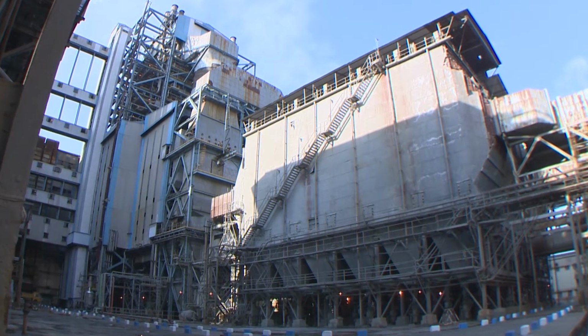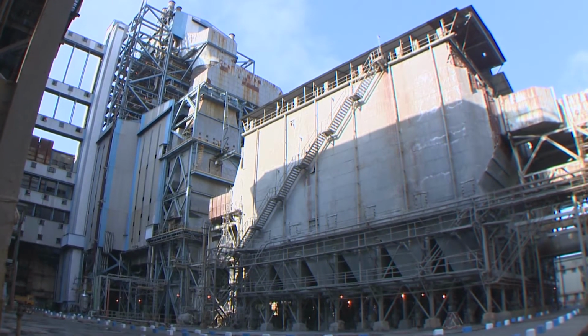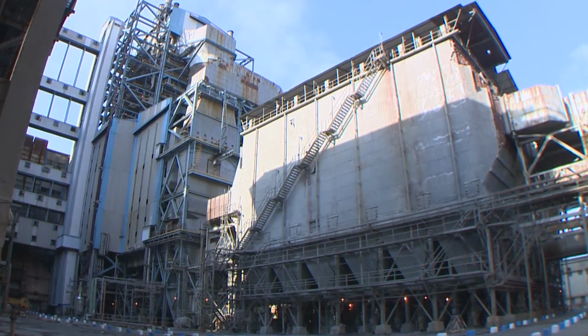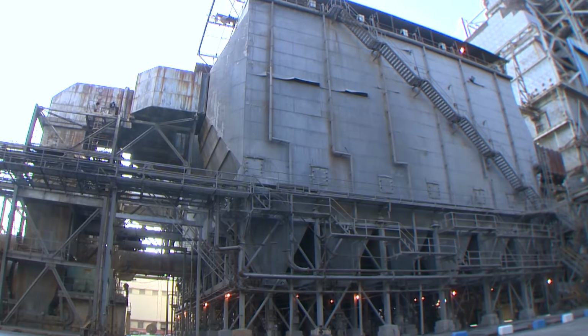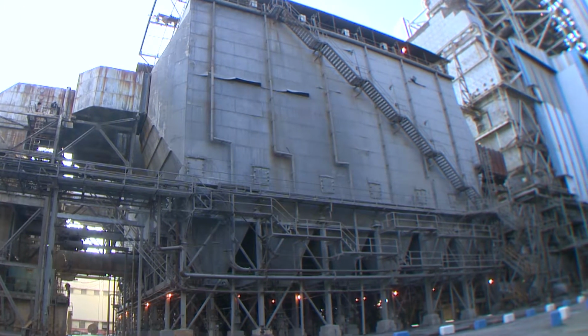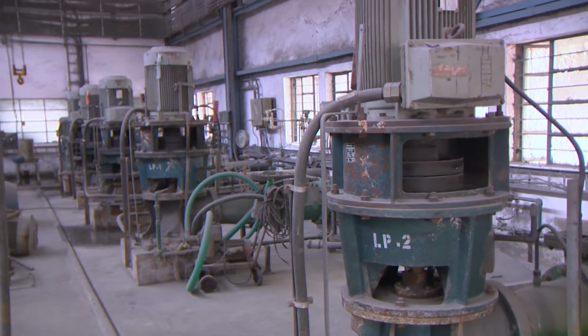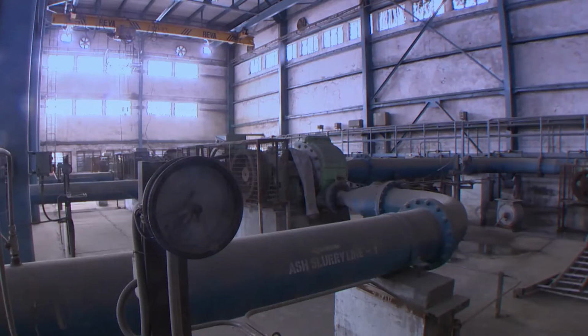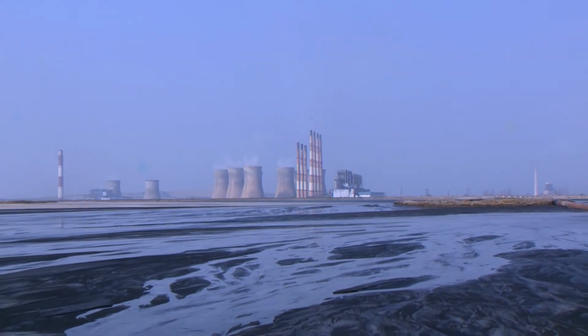The fine ash particles carried along with the flue gas are known as fly ash, which is collected by the electrostatic precipitator and mixed with low pressure water to form slurry. Then the slurry is pumped by the ash slurry pumps into the ash pond.